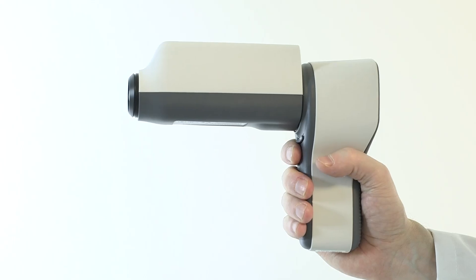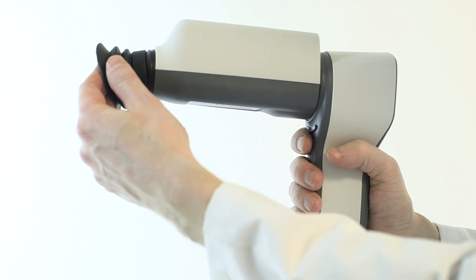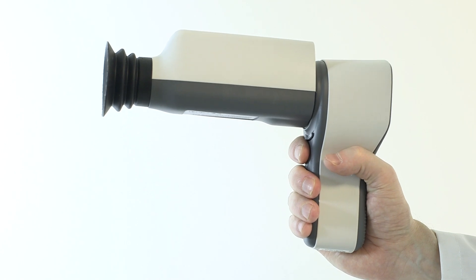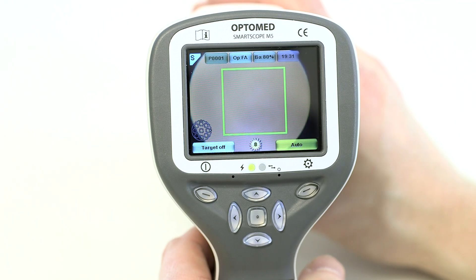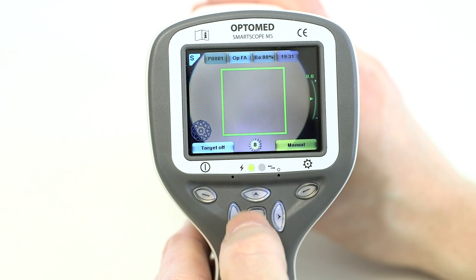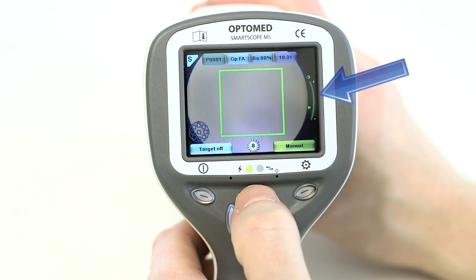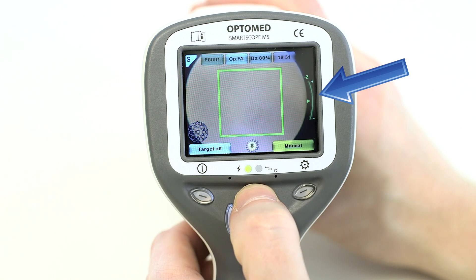The module can be used with an eye cup to give additional stability during imaging. Attach the eye cup by pressing its base around the lens ring. Select the preferred focus mode by short pressing the right soft key.